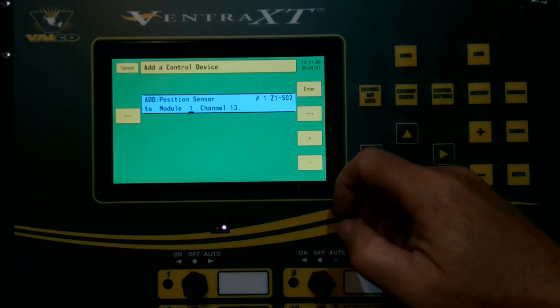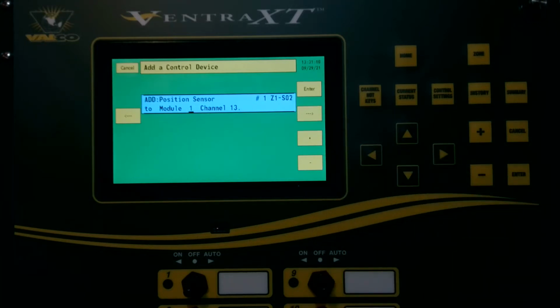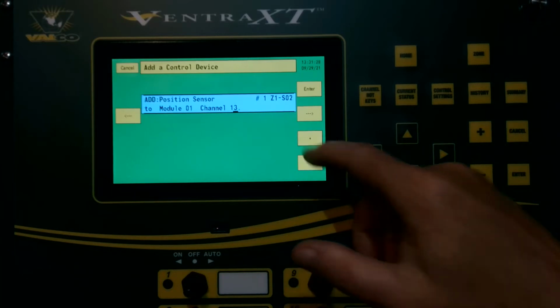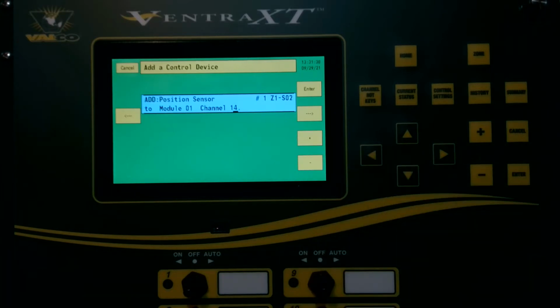Our Ventra XT is a standalone unit, so this particular device will be programmed to module 1, which is on the analog input board on the interconnect board. So it's mod 1, then we arrow over, and the channel we are wired to is channel 14. Then enter to confirm, and then we hit our channel hotkey and it takes us back to our devices. Let's go back to the previous module.